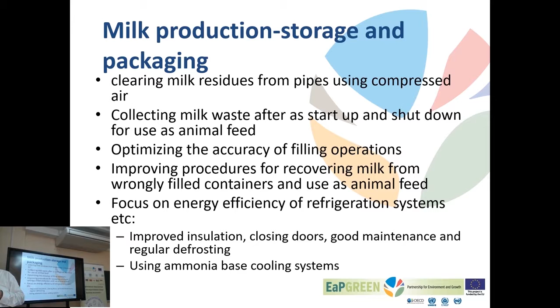Good maintenance, we will discuss in a minute. This includes defrosting in really cold areas, and cleaning condensers to allow air to take away heat from the compressors if we do not recover the heat. In bigger installations, ammonia is a very efficient refrigerant, and we could also do these calculations. Thermodynamically, ammonia is a very good solution. If you do proper design and keep the volume of ammonia in your system low, ammonia can also be a very safe system. But we will discuss refrigeration in a minute.